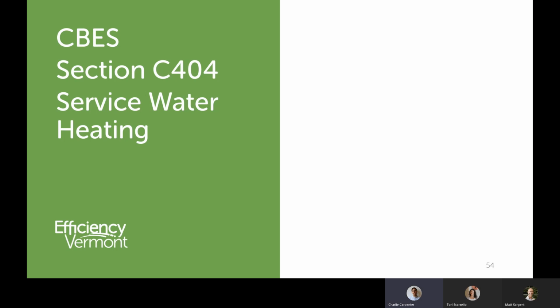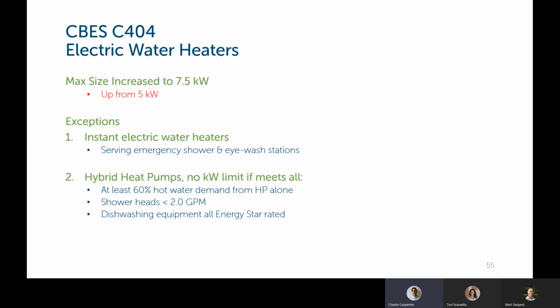So the commercial requirements for service water heating are in section C404. The maximum size of an electric water heater has been increased from 5 kilowatts up to 7.5 kilowatts. Some exceptions to that are any instant electric water heaters that are serving emergency shower or eye wash stations. Those can be larger. Or hybrid heat pump water heaters do not have a kW limit. If you meet all of these requirements, you need to have at least 60% of the hot water demand coming from the heat pump function of the water heater alone. Any shower heads in a building must be less than 2 gallons per minute, and any dishwashing equipment in the building must be ENERGY STAR rated.